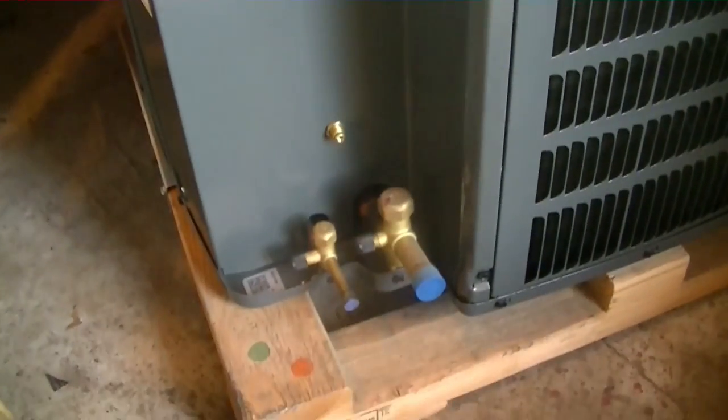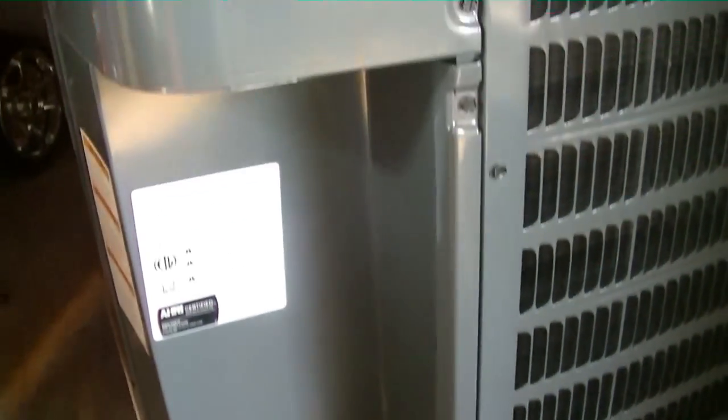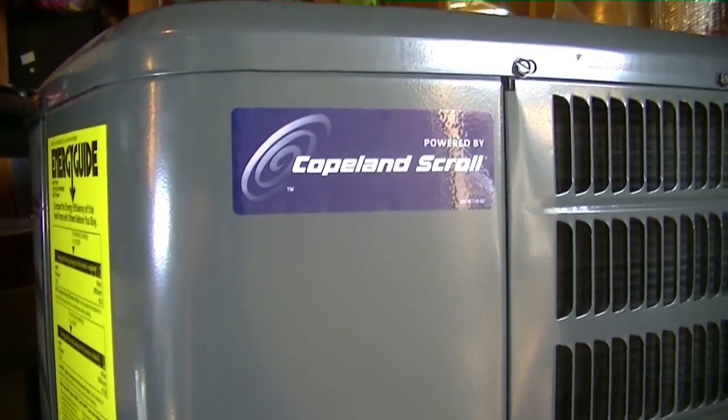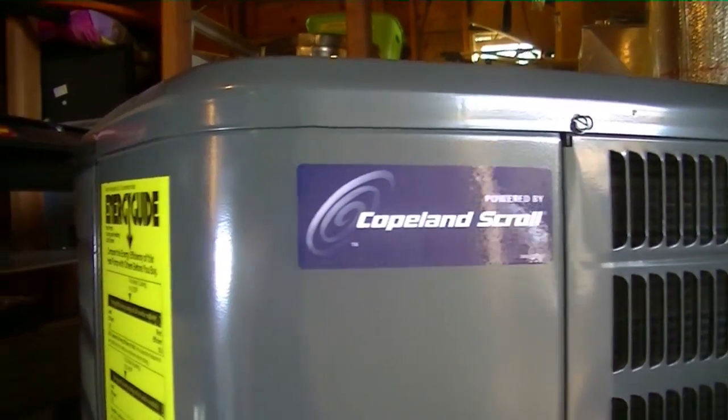This one actually has no pressure on it. The supply house periodically gets in units that are damaged and have a problem. This one has a leak on the condenser U-bend that just wasn't brazed in properly from the factory.